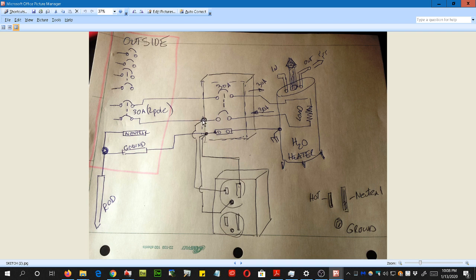So when the electricity flows off this phase into this one, and then it goes through his little light, like a little load across here, and it flows back here, it has no phase to get back to like you would have with the 2 poles. So it's on the ground, and it goes all the way back to the ground. So it goes through this ground wire. Could be the copper pipe, who knows, whatever he's got going on in the house. So you don't want ground currents. Zero, none, zero, bad, bad, bad. You want to make sure that that current gets back to a neutral. That's the problem he had.